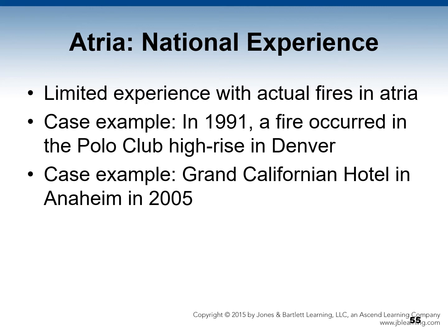In regards to atria and national experience, there is limited experience with actual fires in atria. However, there is one case example in 1991. A fire occurred in the Polo Club high-rise in Denver. Although the building had an atrium, it had no sprinklers and no smoke control system, only skylights at the roof.